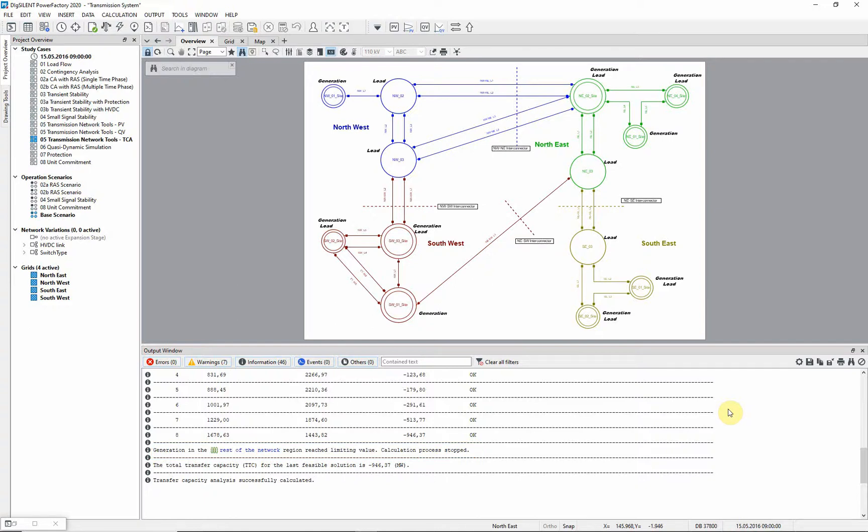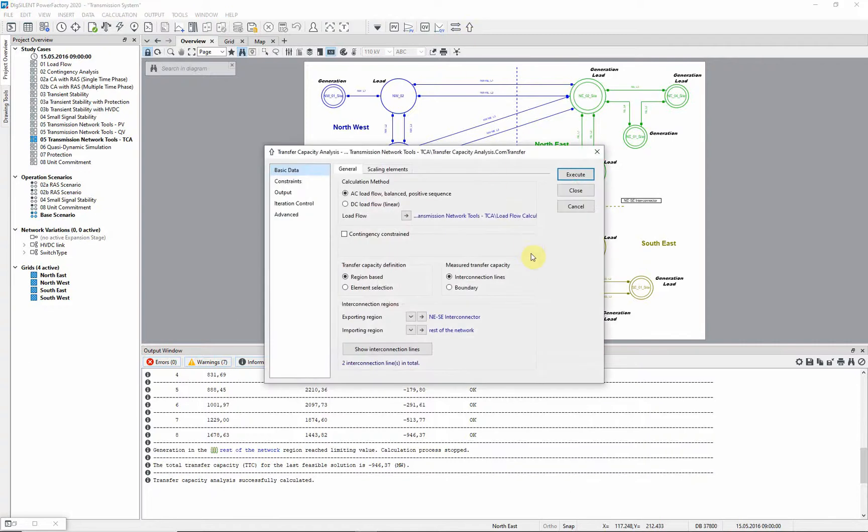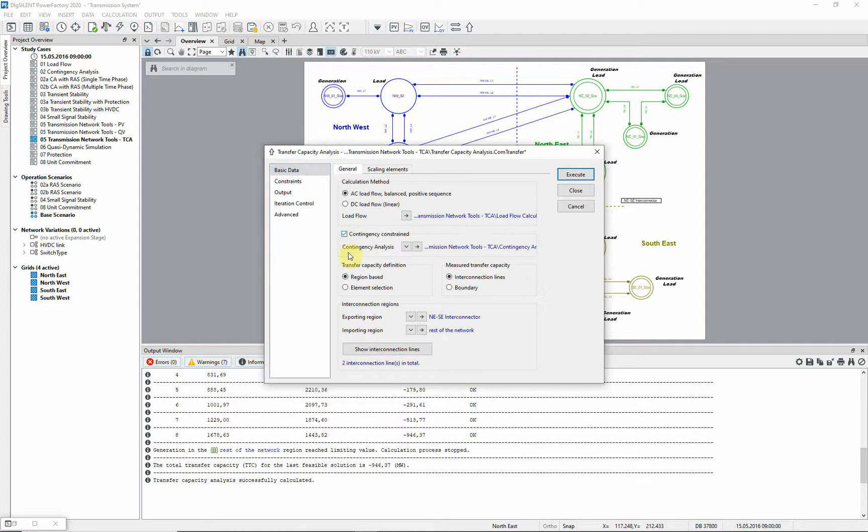In reality, the transfer capacity across a boundary may be limited by the impact of potential faults on the network. Returning to the transfer capacity analysis dialog, we can see that there is an option to consider contingencies. If this is selected, the contingency analysis dialog box is made available.